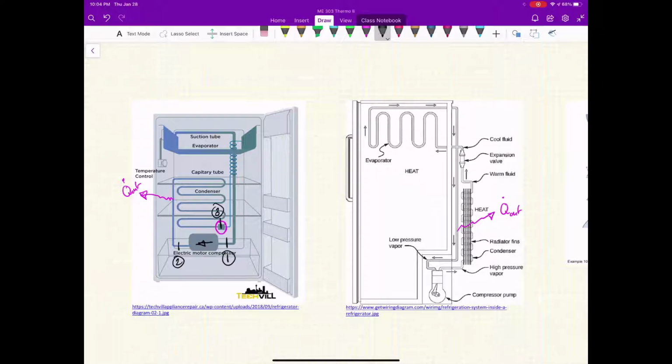Instead, what you see is this tiny little tube, and this is why I like this picture, because this is the setup that you're most likely to see every day on your actual refrigerator. This little tube right there is a capillary tube. It's basically a tube that's there to provide friction. Think of it as a throttling valve, if you will, which is all friction. And the point of that is to drop the pressure. And since you're starting out with a saturated liquid, you're actually cooling the fluid down significantly in the process, even though it's a little counterintuitive, given that you're flowing through a tube with friction.